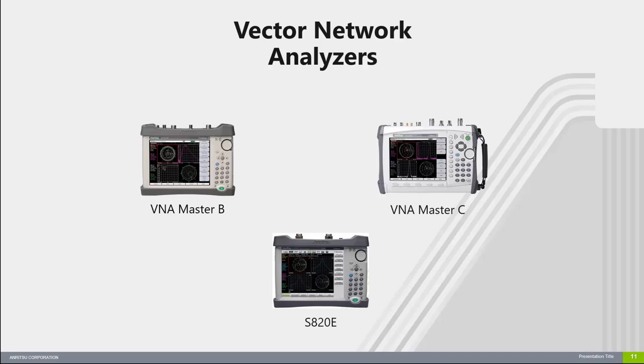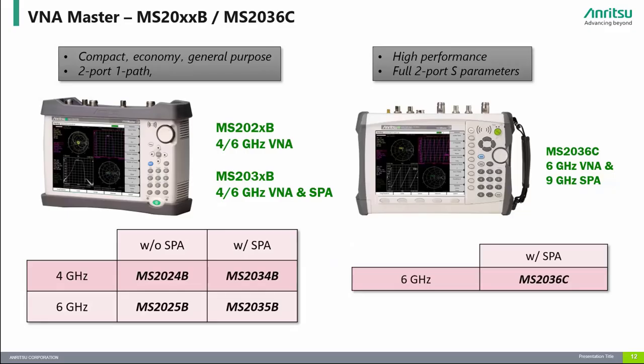Let's take a look at Anritsu's handheld vector network analyzers. The B-Series VNA Masters are Anritsu's economy VNA solutions. The MS2024B and MS2025B are two-port, one-path instruments covering 4 and 6 GHz frequency ranges and do not include a spectrum analyzer. If you need a spectrum analyzer, we offer the MS2034B and MS2035B. The MS2036C VNA Master is Anritsu's high-performance fully reversing two-port VNA with frequency coverage from 5 kHz to 6 GHz, and also includes a full-featured spectrum analyzer covering 9 kHz to 9 GHz.